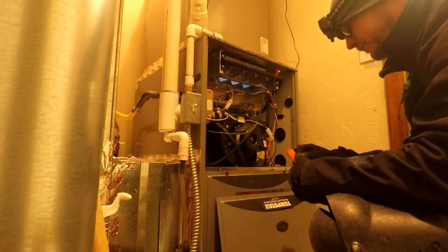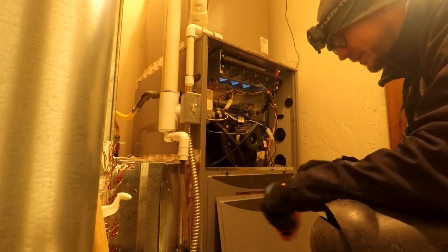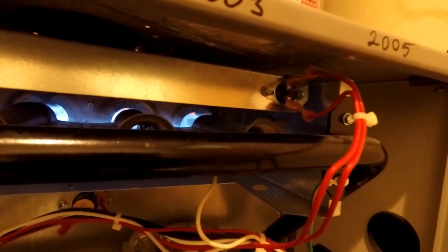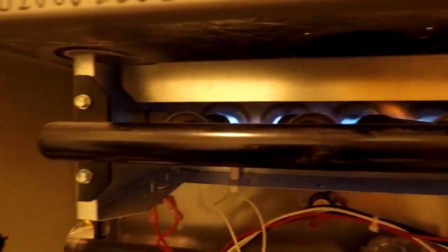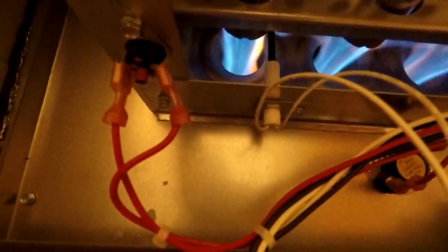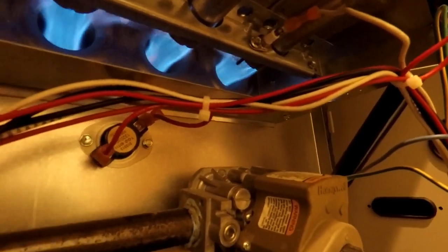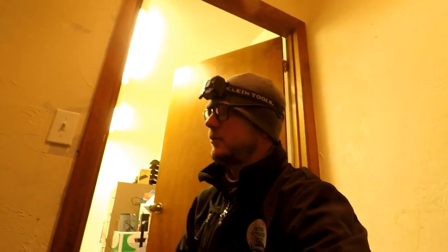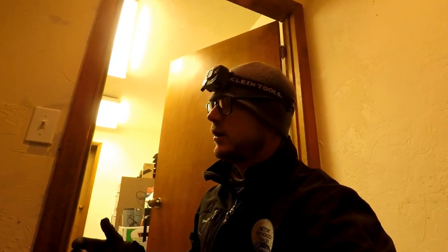Okay, this thing's been running for like 15 minutes, almost 20 minutes, and it has not even started to roll out that flame. I mean, everything's shooting right down the pipes like it should be, not one bit of flame rollout. So I don't know why this rollout was tripped, but it was. So I think at this point we're going to go ahead and let it run. I had the gal come in here and I showed her the rollout switches and everything, explained to her what was going on, explained to her different things that could cause it, and basically how to at least reset that in an emergency to get her by until we can get out here if it does it again.